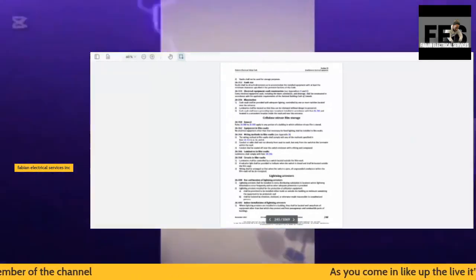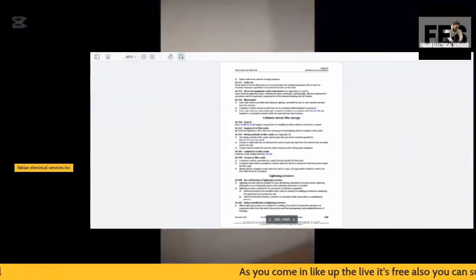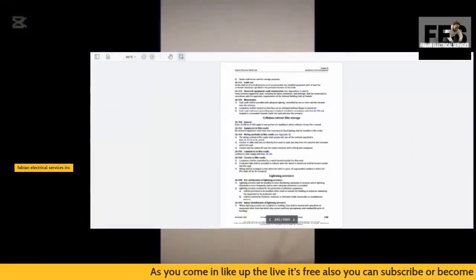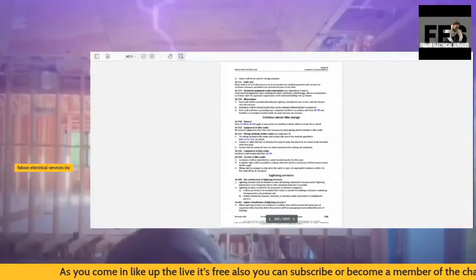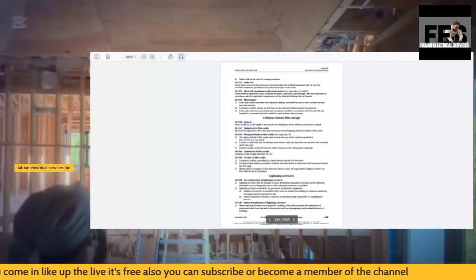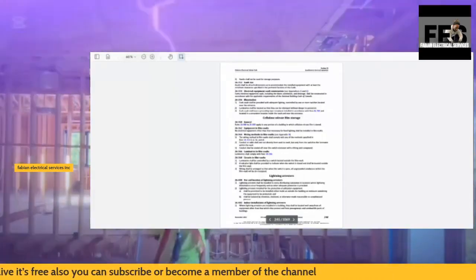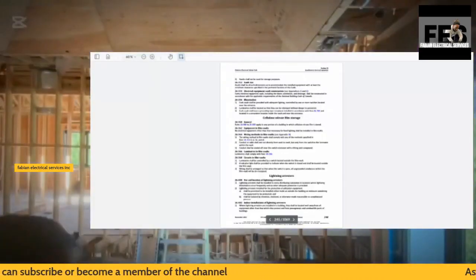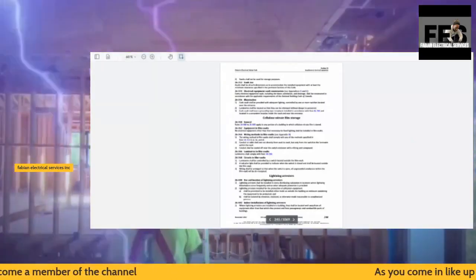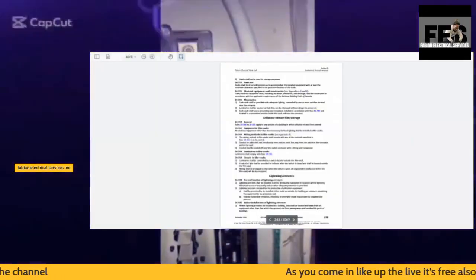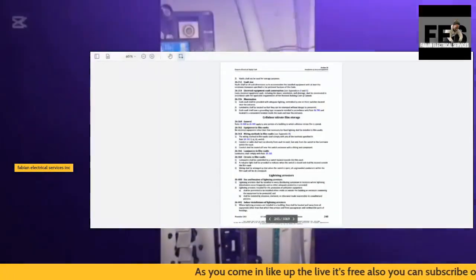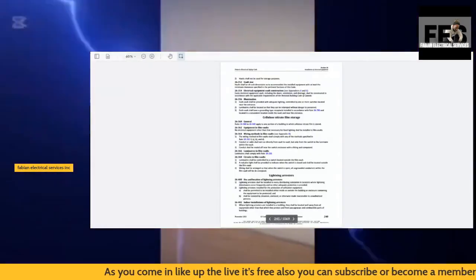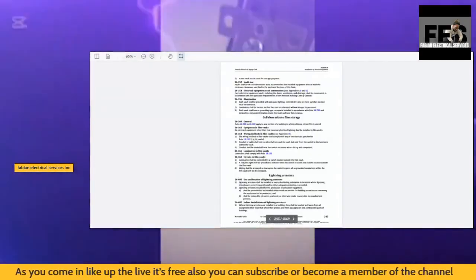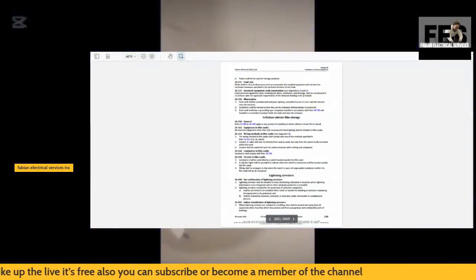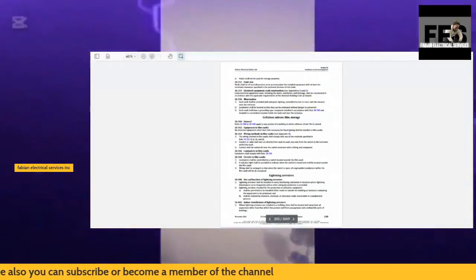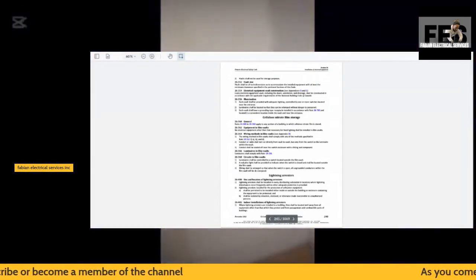So again, sub panels must be installed in a readily accessible and protective location, not in bathrooms or clothing closets, and with adequate working space, minimum 36 inches in front and 30 inches wide. As I said, permits and inspections. A permit is required for sub-panel installation, and the work must be inspected by the Electrical Safety Authority, ESA, to ensure compliance with the code.